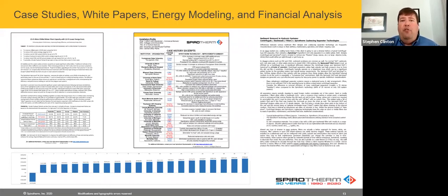After removing air and the dirt from the system, not only did our differential pressure decrease by 35 PSI, not feet, 35 PSI, he said, we don't have the air, we don't have the dirt, we don't have the clogs, we don't have the hot and cold calls we used to. Those are some of the things we can do.